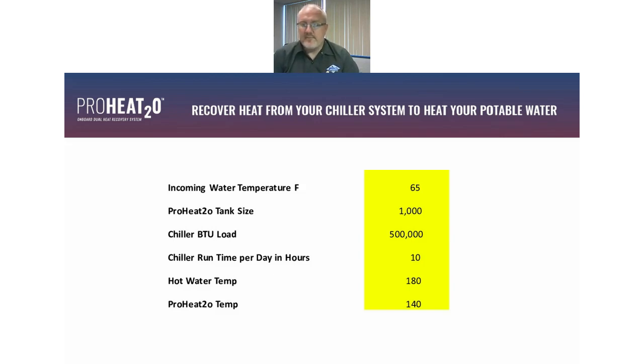Because with heat recovery, we're only going to generate and build hot water if the refrigeration circuit is running. So then we look at what kind of a maximum hot water temperature are we after, and where can we get to with the ProHeat2o? How warm can we preheat that water to? So in this example, we're getting it to 140 and then taking that hot water temperature up to 180 after the heat recovery has been in place.